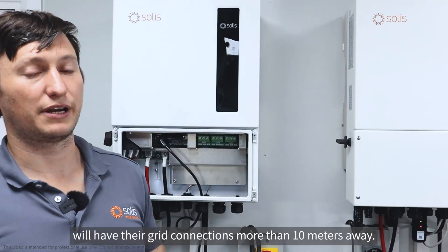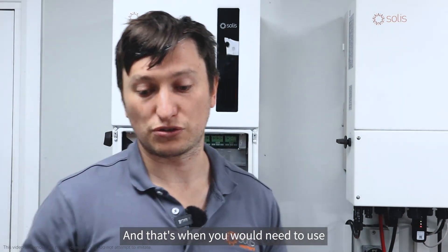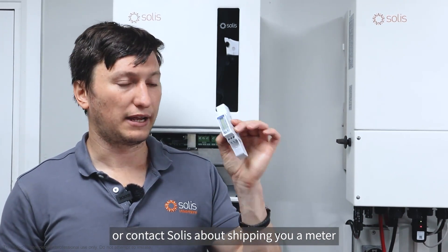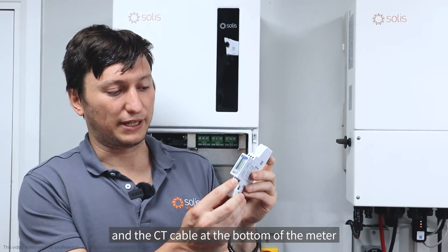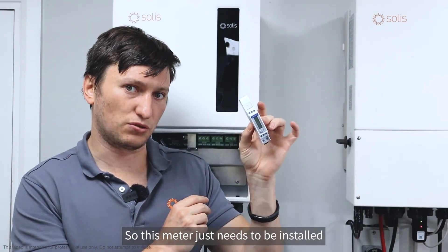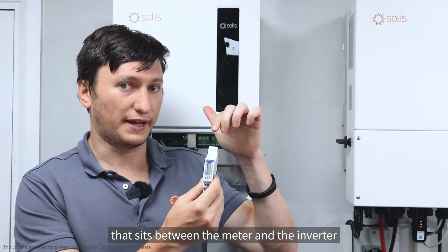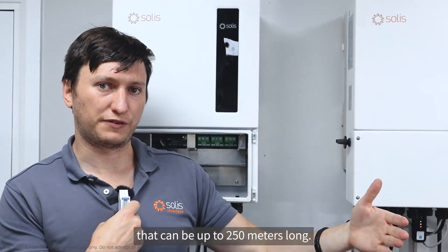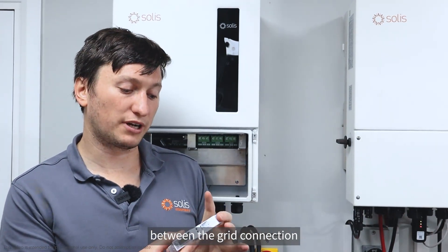A lot of installations will have the grid connection more than 10 meters away — for example, 50 or 60 meters. That's when you would need to contact Solis about shipping you an Eastron single-phase meter for single-phase installations. You install this meter at the grid connection, keeping the CT cable at the bottom of the meter within 10 meters. The analog signal must stay under 10 meters. From the meter to the inverter you use an RS-485 communications cable, which can be up to 250 meters long — giving you up to 260 meters total between the grid connection and the inverter.